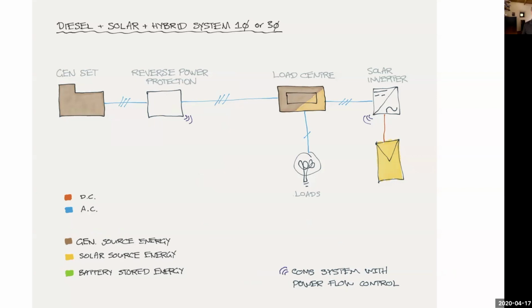Because solar inverters have a special power, which is they can synchronize with another source. So they'll see the generator's frequency and monitor it. They'll match it internally before they parallel with it. So they're watching the frequency and voltage. They synchronize on the 0 volt crossover point, close their paralleling contactor, and work in unison with it. And then they can start to flow power in the reverse direction back towards the load center.